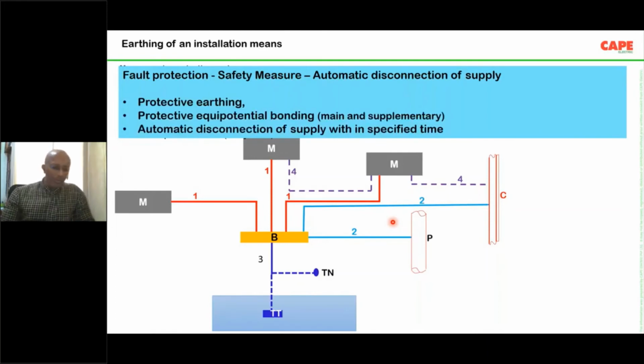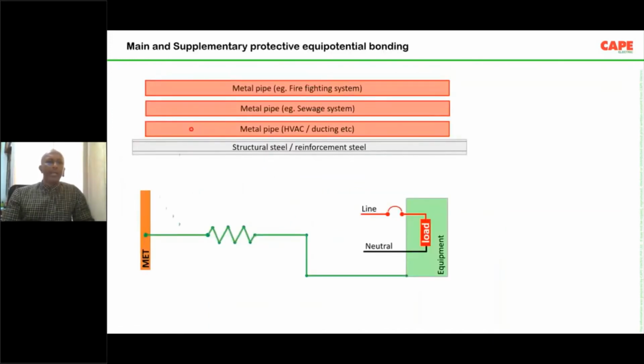So if you read any standard or a technical book, you will only see automatic disconnection of supply. You will not see the other three, because it is understood that if anybody says automatic disconnection of supply, it is achieved by protective earthing, protective equipotential bonding, and automatic disconnection of supply. These are very well explained in the standard. Then what do we mean by protective equipotential bonding? It means at the origin of the installation, that means at the main distribution board, this is the earth bus bar of the main distribution board.